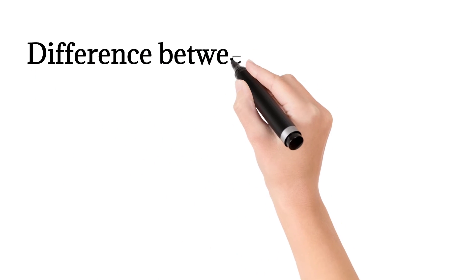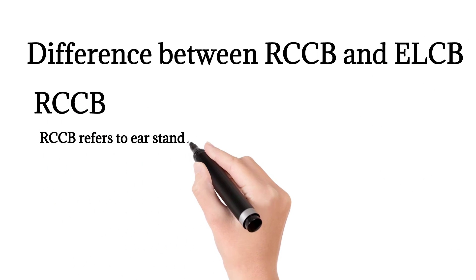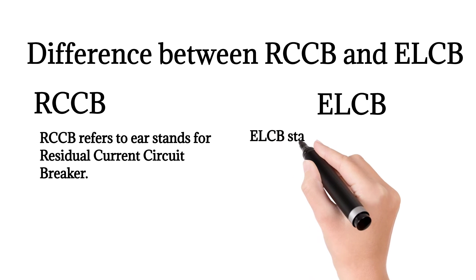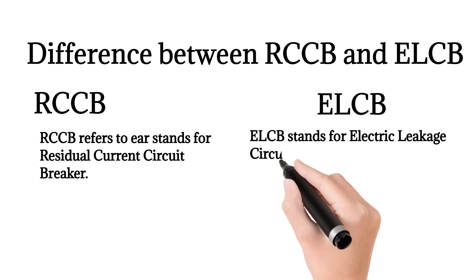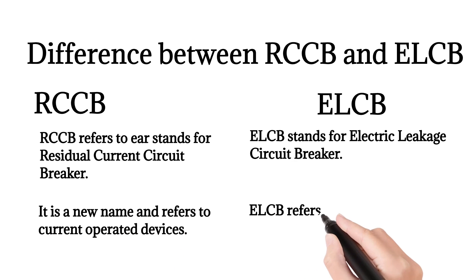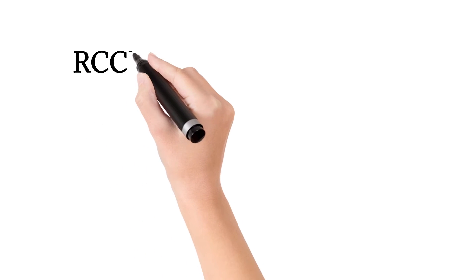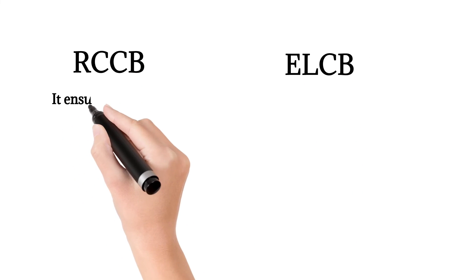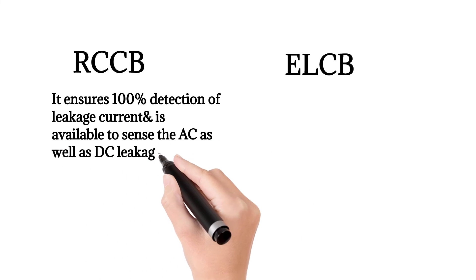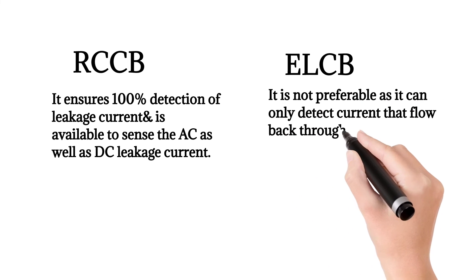Comparing RCCB and ELCB: RCCB stands for Residual Current Circuit Breaker; ELCB stands for Earth Leakage Circuit Breaker. RCCB is a new name and refers to current-operated devices, while ELCB refers to voltage-operated earth leakage devices. RCCB ensures 100% detection of leakage current and is able to sense both AC and DC leakage current. ELCB is not preferable as it can only detect current that flows back through the main earth wire.